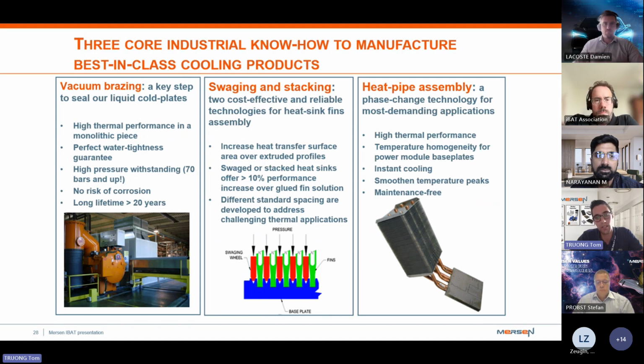In the middle, this is the technology we use for our air cooling. It's called swaging and stacking. This helps to have a custom-made solution on the fins, in the height, the length, and so on, in order to increase the heat transfer surface and allow more complicated designs than an extruded air cooling solution. So it's really custom made in comparison with extrusion and allows more performance with more complex design.